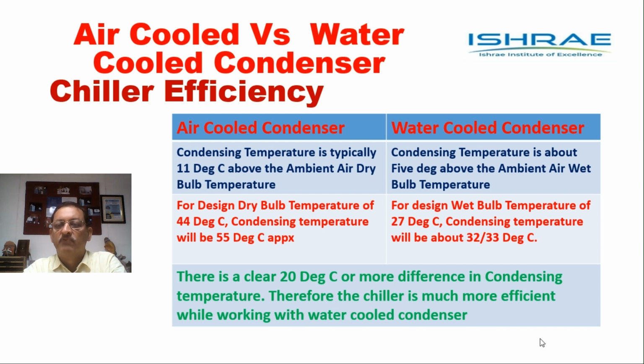On the other hand, when we have water cooled condenser, the condensing temperature is about 5 degrees centigrade above the ambient wet bulb temperature. Now, there is a difference. On the left hand side, in air cooled condenser, I talked about dry bulb temperature of ambient air. On the right hand side, I talked about wet bulb temperature of air. The design wet bulb temperature of air in Delhi will be around 27 degrees centigrade. The condensing temperature will in that case be around 32 to 33 degrees centigrade, whereas when we have an air cooled condenser, the condensing temperature will be almost 55 degrees centigrade.